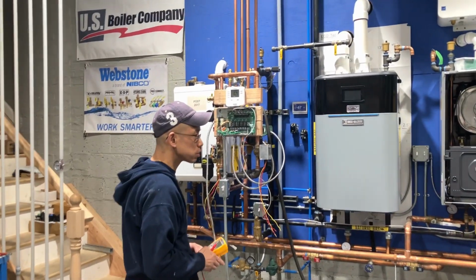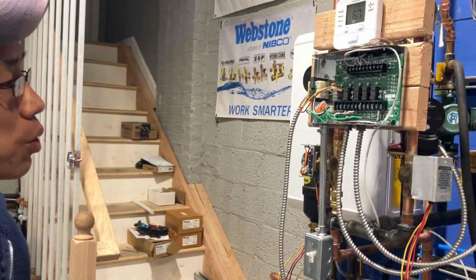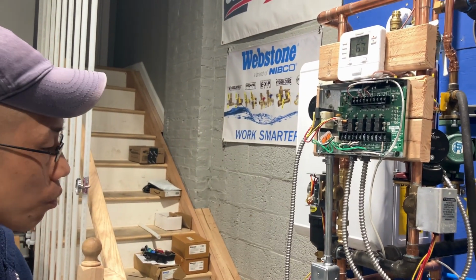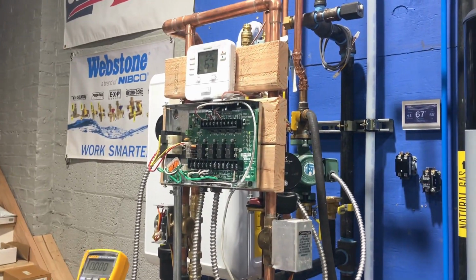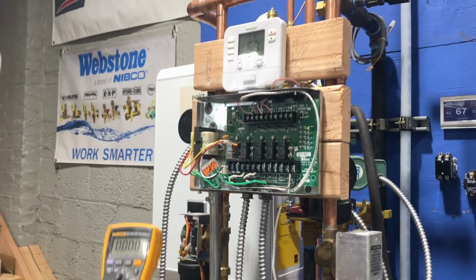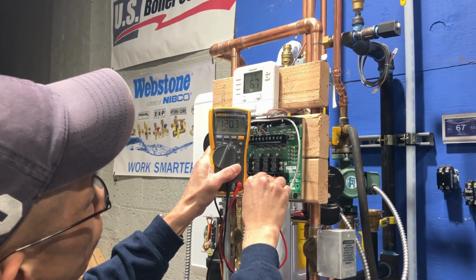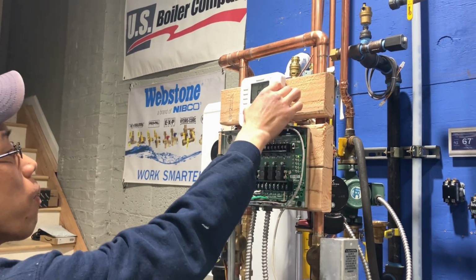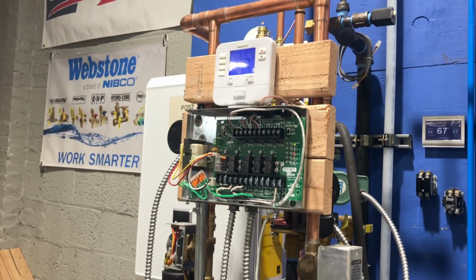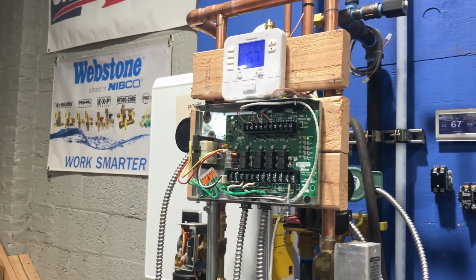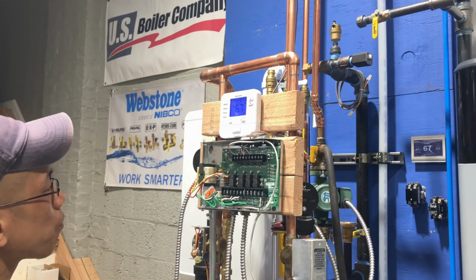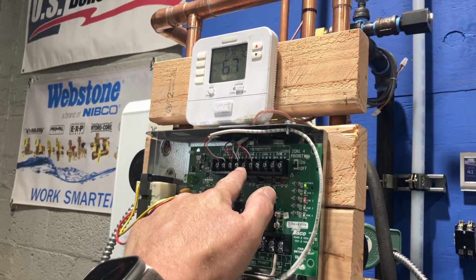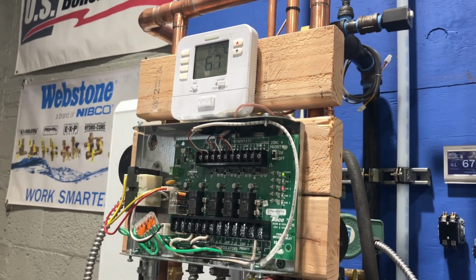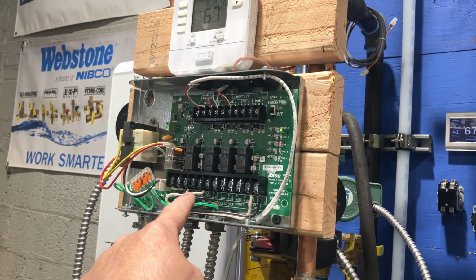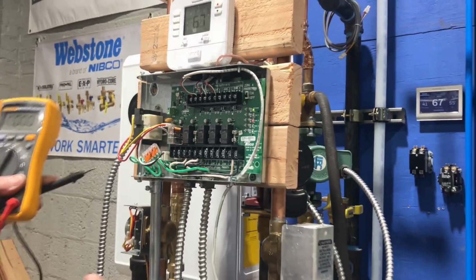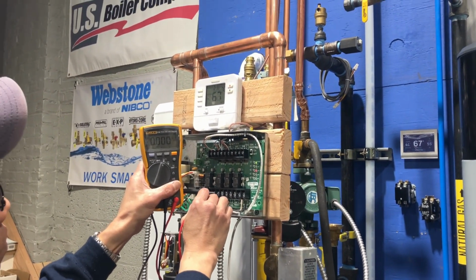I'll make sure the power's on and test the power's going to this board. Okay. Good. Test away. Power's on. You have a green light on the power. You have 120 volts there. Okay. Now you have a call for heat. Okay, the red light is on zone 2. All right? That means the thermostat is closing the circuit, and R and W for zone 2 is energized. Right. Okay? So you should have 110 volts on zone 2. Let's test for zone 2, 110 volts. And you have nothing there.